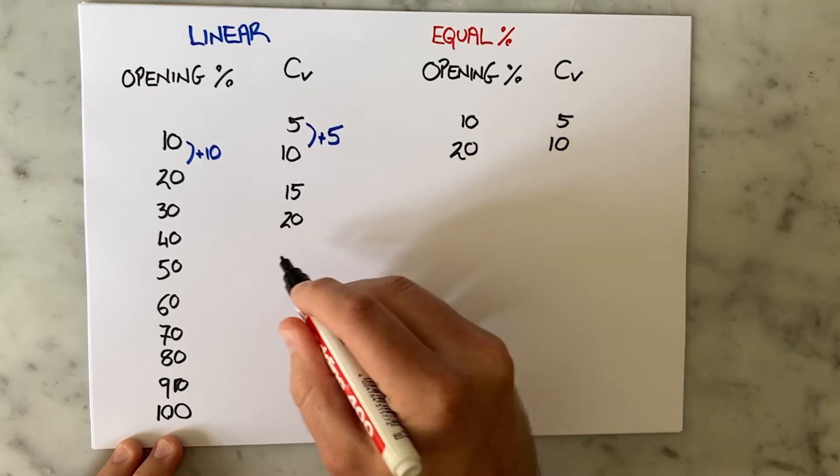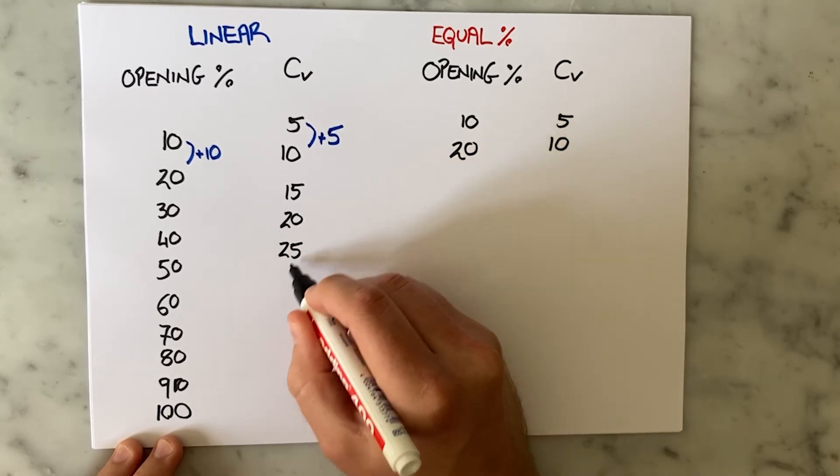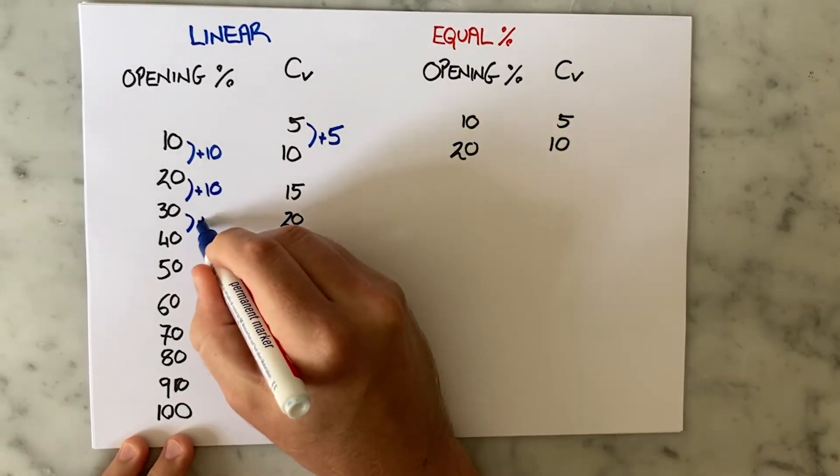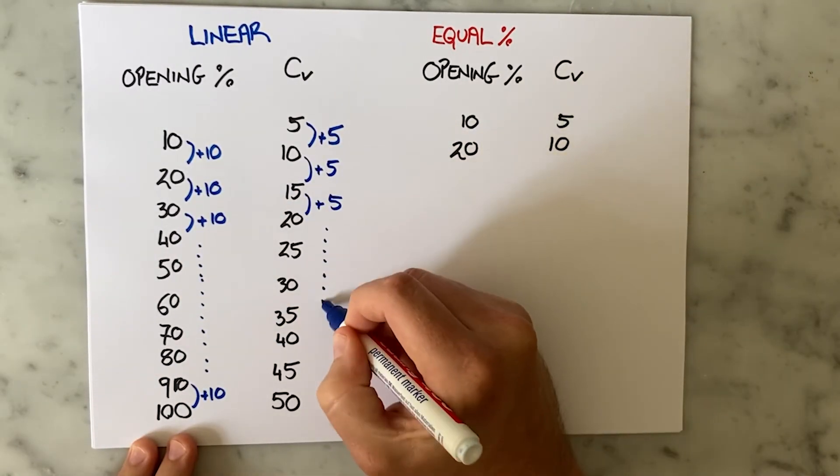At 40% opening it goes up another 5 to 20. I carry on like this until the valve is 100% open and I see that this valve has a CV of 50.